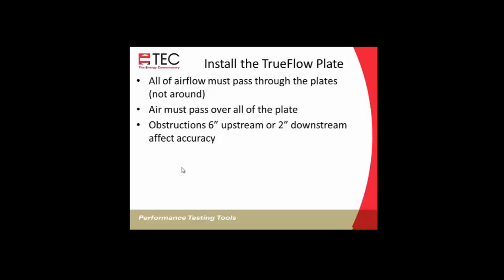You want no obstruction 6 inches upstream or 2 inches downstream. That can affect the accuracy. So the air handler's downstream. If that's less than 2 inches away, that could be problematic. So 6 inches upstream, 2 inches downstream. It can be installed right inside the air handler cabinet. You can tape it in place or wedge it in place as long as no airflow is going around it and all the airflow is going through it. You could install it inside the air handler cabinet, as long as you have at least a 2-inch space between the TrueFlow and the air handler fan itself.